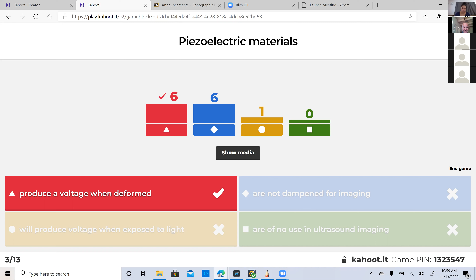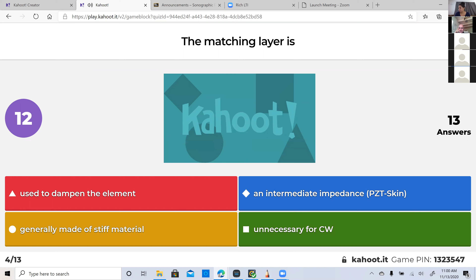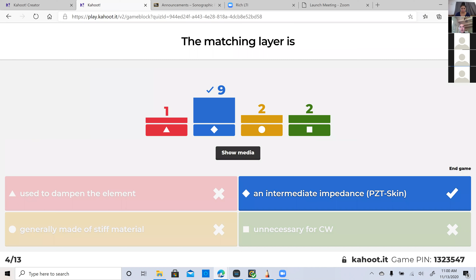The matching layer is good. Most of you have an intermediate impedance between the element and skin. Definitely not made of stiff material. It's actually made of a rubbery material. Once again, halfway between skin and the element itself. Still in the lead.